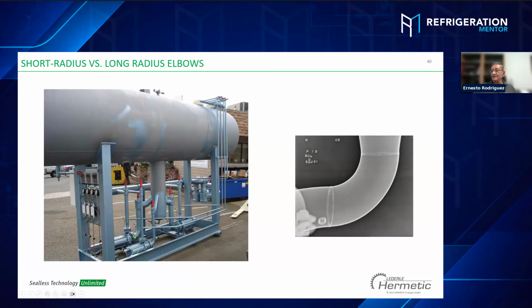You see the elbow right here, right at the pump, and you can see in these X-rays how the turbulence is going to the suction of the pump. So that was a question we had: what's most preferable for the suction, long or short radius bends? The best case would actually be moving the pump probably 2 or 3 feet away with a straight run, and then a long radius elbow, not right at the pump. Correct.